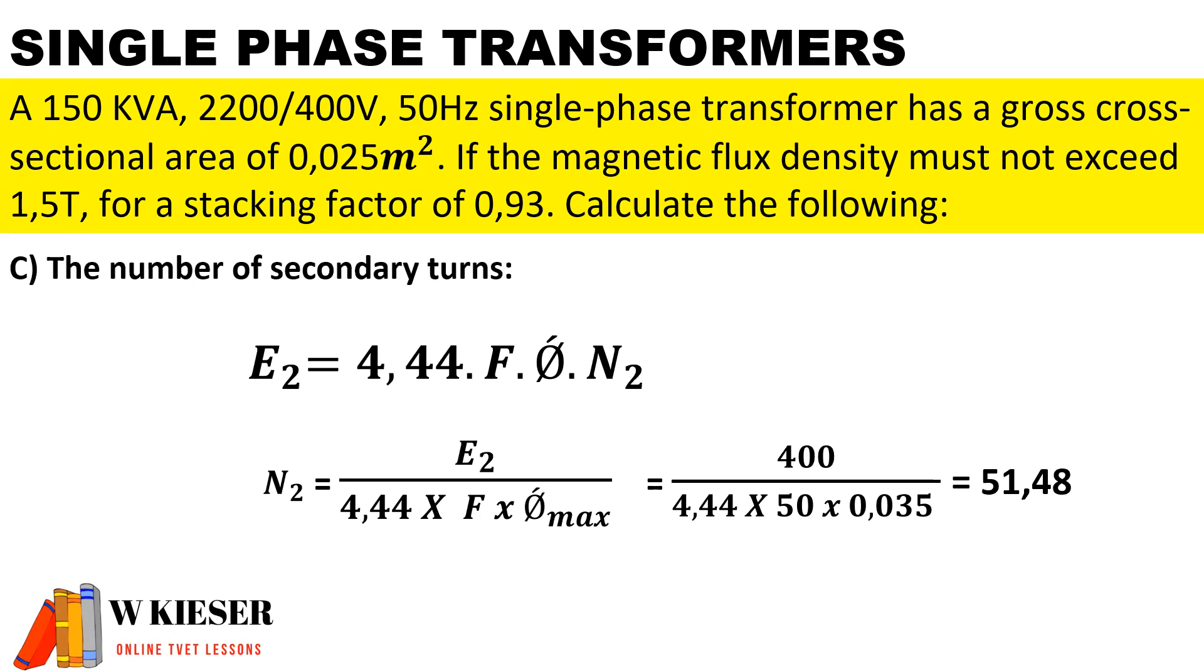To calculate the number of secondary turns, we'll use the EMF on the secondary side of 400 volts divided by 4.44 and divided by the frequency of 50 hertz and the maximum flux of 0.035. If you round it off, the number of turns on the secondary side will be 52.